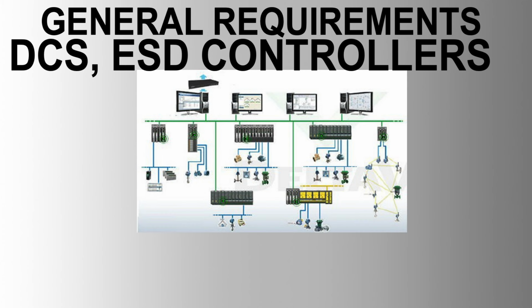Marshalling cabinets. Design and configuration. Equipped with field terminal blocks, FTB, and field termination assemblies, FTA, to mirror field junction boxes and I/O boards respectively. Used to crosswire signals between FTB and FTA. Interconnection via pre-wired and pre-tested system cables with multi-way connectors. Field terminal blocks should be cage clamp interruptible or equivalent terminals with necessary polarity distribution, switching, and protection, test points, and earthing systems.